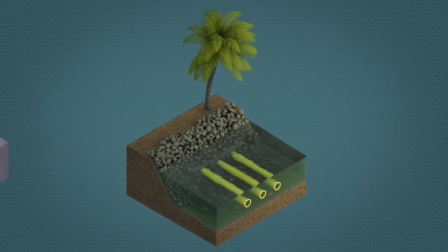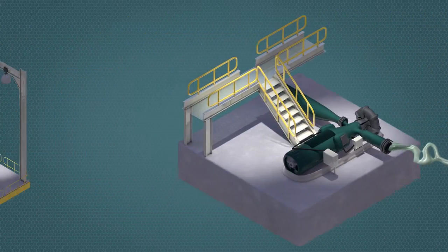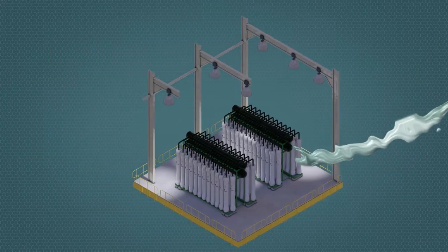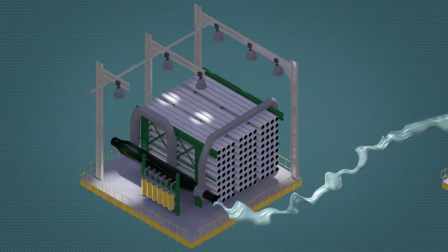The desalination process starts by drawing seawater from the Gulf that enters the plant through intake pumps. The seawater is then pumped to state-of-the-art ultra-filtration units. Ultra-filtration membranes provide effective pre-treatment for the RO membranes, thus increasing the reliability and longevity of the system.